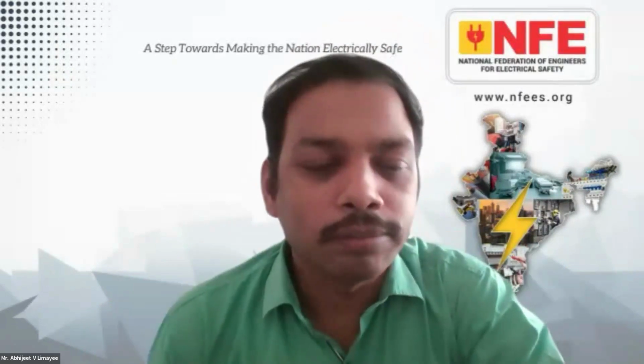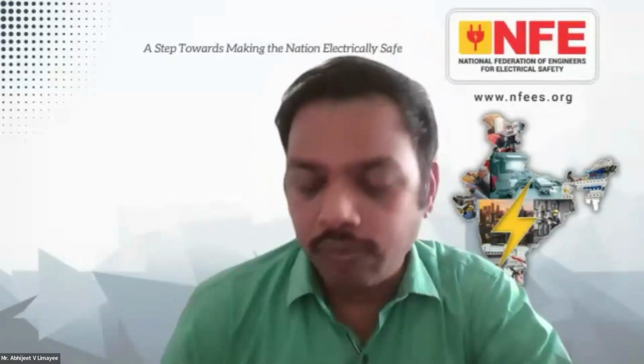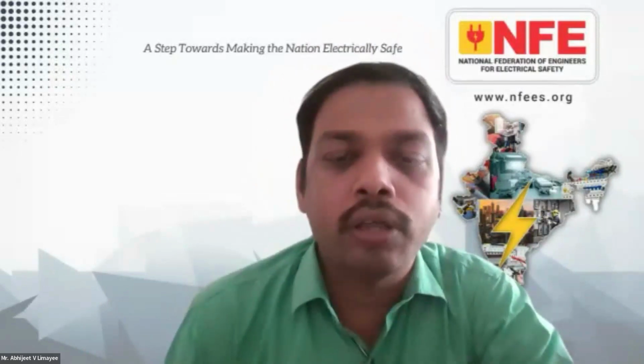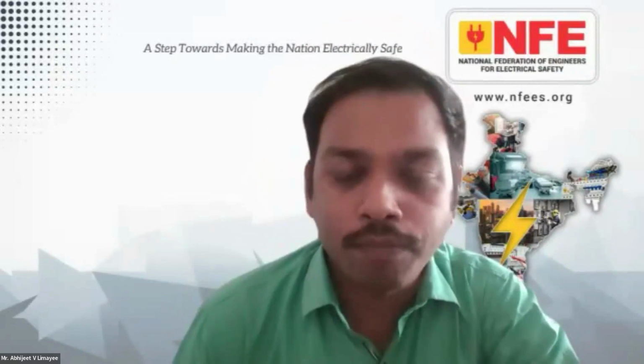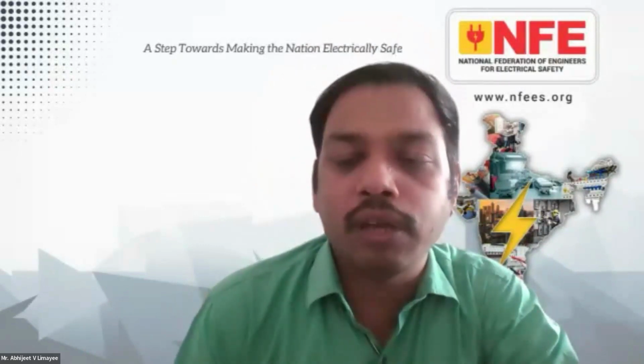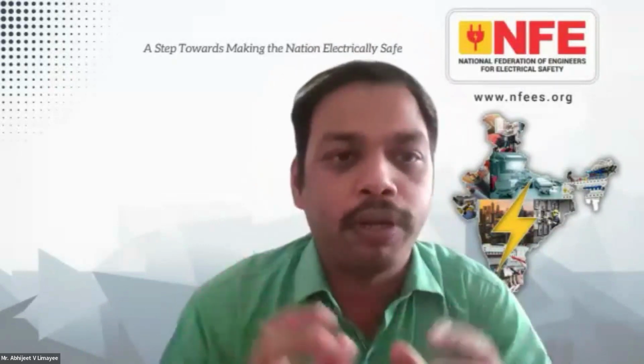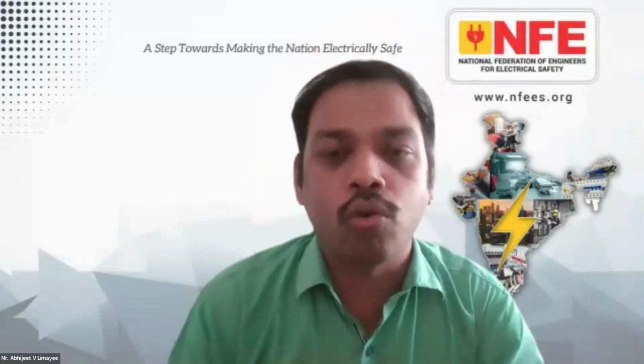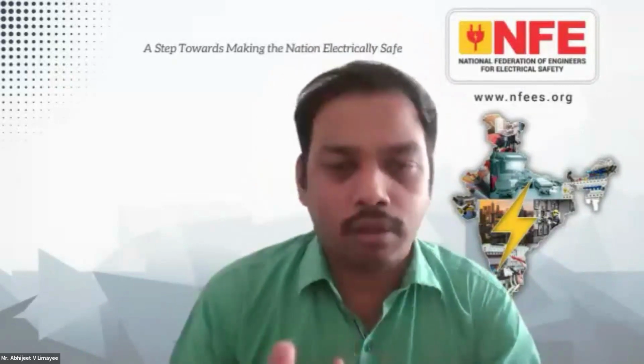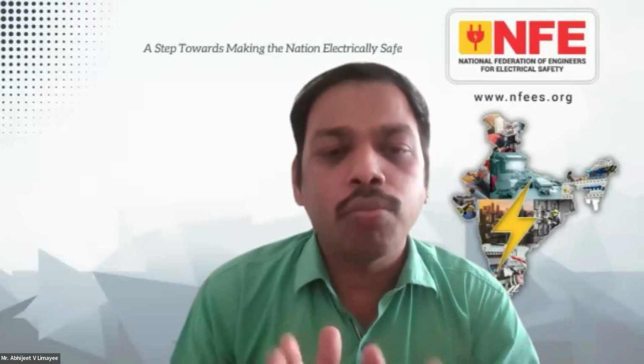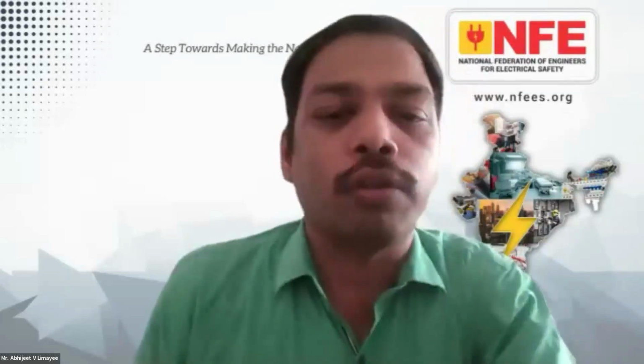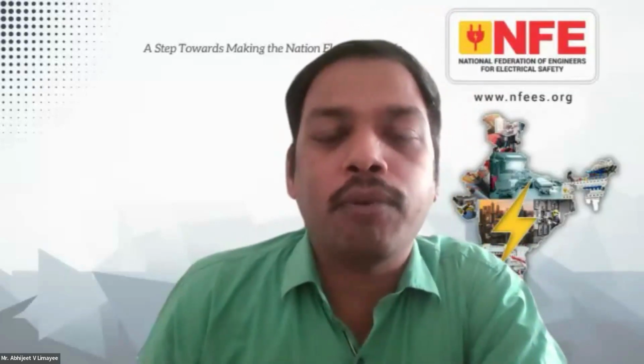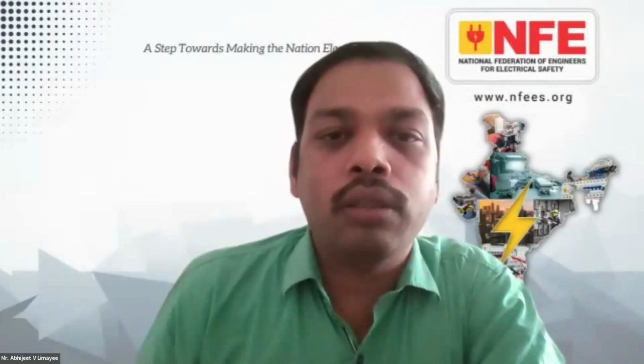Thank you, Gopaji, on this. So, typically, when we look at such a device, and when we look at IoT, as you correctly pointed out, IoT is a very good tool for data collection and communication. However, using IoT for safety has some limitations. Typically, when we look at a hospital, we know that there are three different groups: Group 0, Group 1, Group 2. Now, if we look at the parameters in isolation, these would typically work in a Group 0 location. However, a Group 1 location might have a backup from a DG, and a Group 2 location might have backup from a DG as well as UPS, where whether these backups should turn on in case of a fault or not, and what kind of signaling from the backup sources should also go to the IoT.